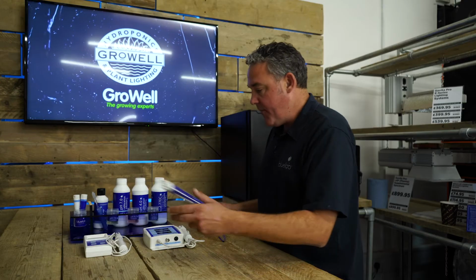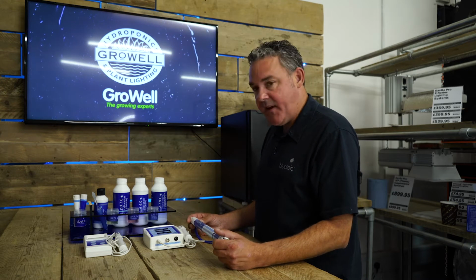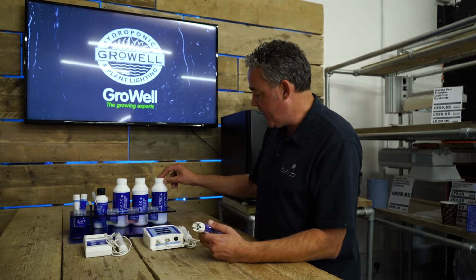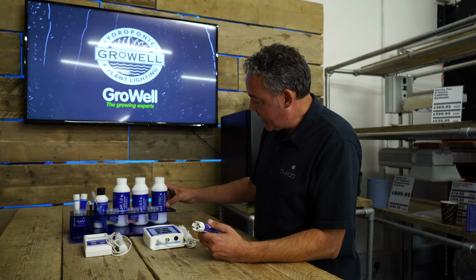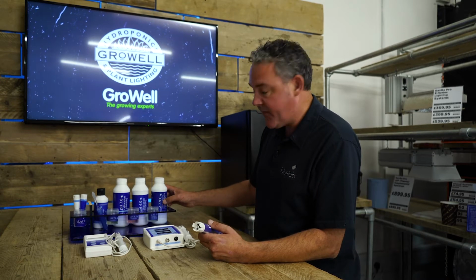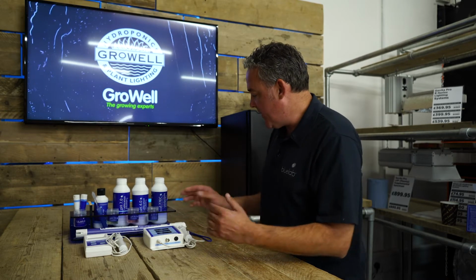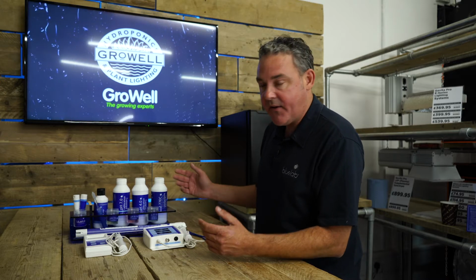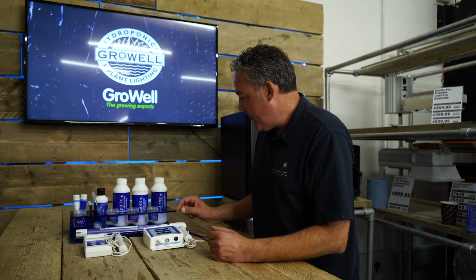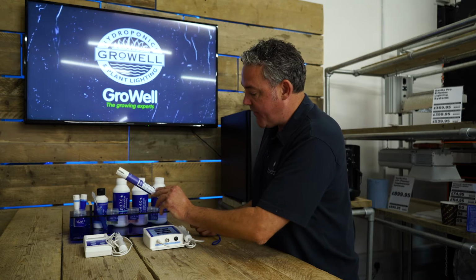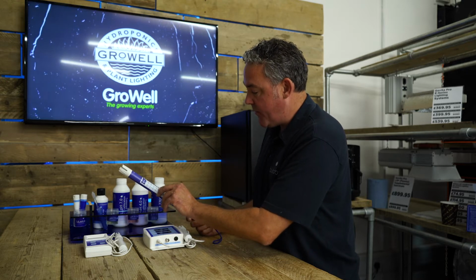A question we get asked a lot is, do I need to calibrate or replace my EC probe? And the answer is no. All you need to do is regularly test your EC probe in a solution of a known standard. So this is a conductivity standard solution of 2.77 EC. There's different ones out there, but as long as it's a known solution, that's fine. We recommend 2.77. With the truncheon, that'll be reading between 2.6 and 2.8.